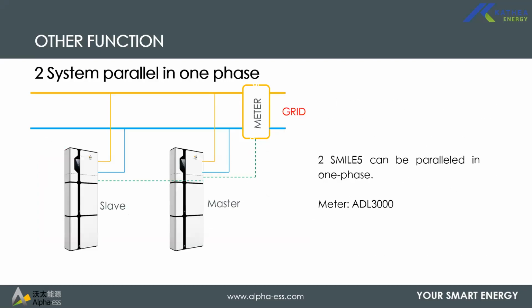And then the second scenario is paralleling in a single phase. You can parallel up to two inverters on a single phase. It means your live and neutral are common to both inverters. On the power side, you would need only one meter, a single-phase meter or a three-phase meter, and that meter is wired to the master inverter. Then the inverter is daisy chained to the slave inverter through those RJ45 components that we spoke about. You would then need to activate parallel mode in the inverter settings. Under function, you select parallel and specify whether the inverter is a master or a slave.